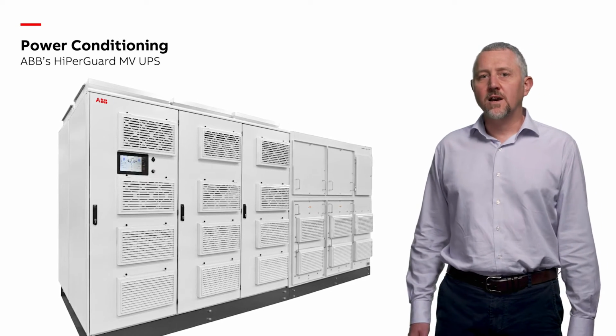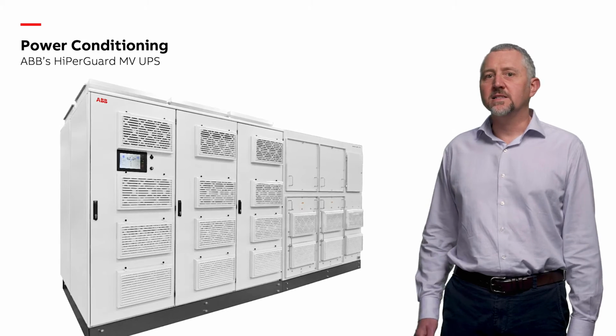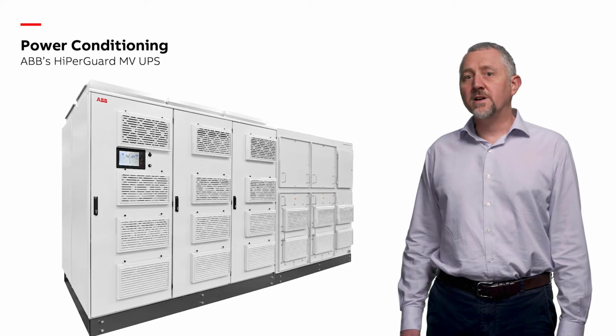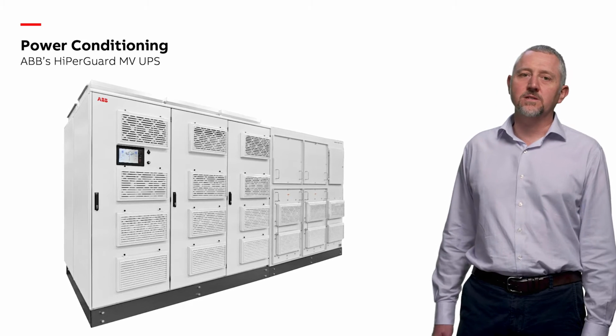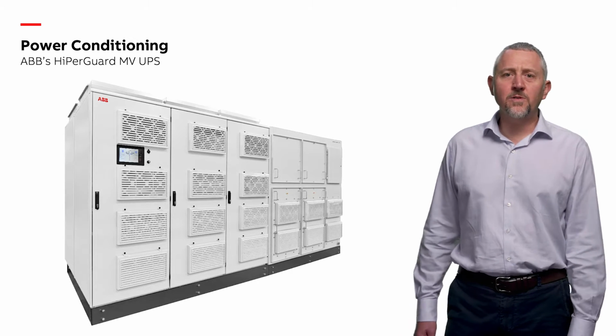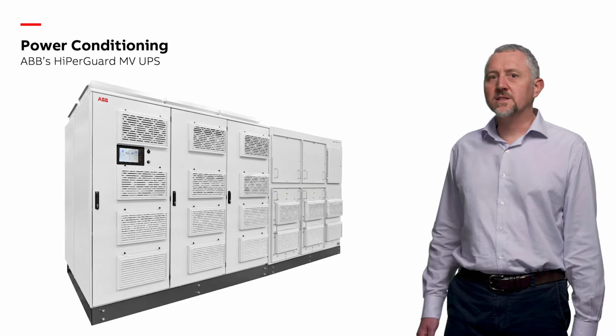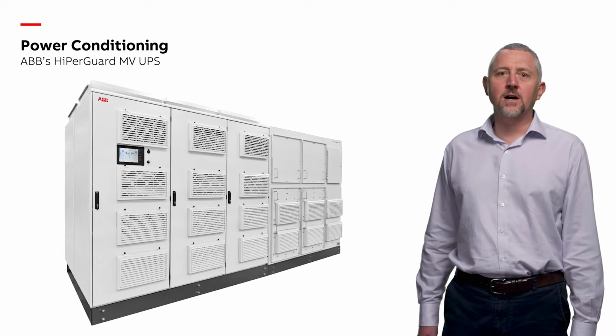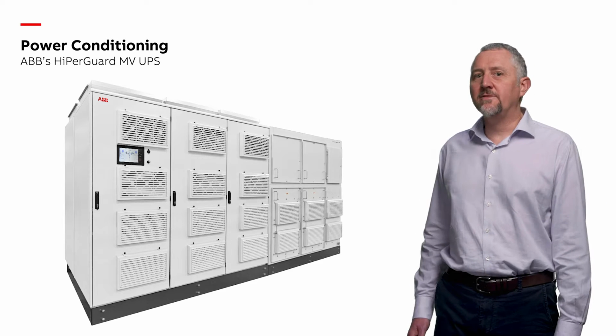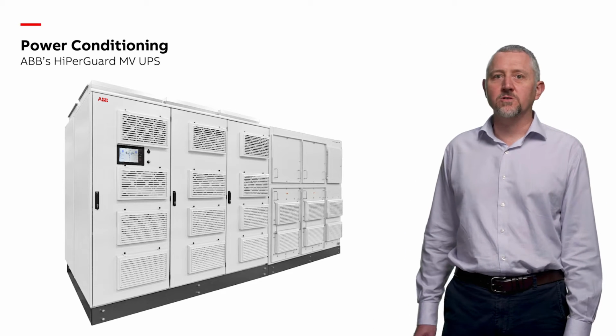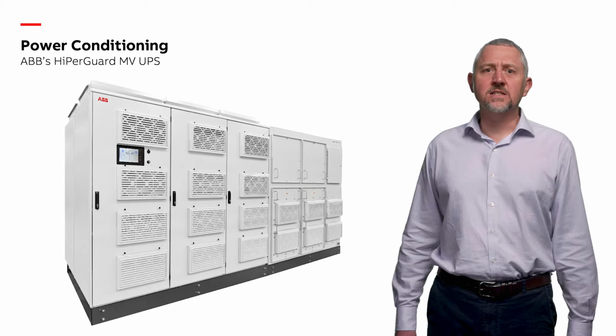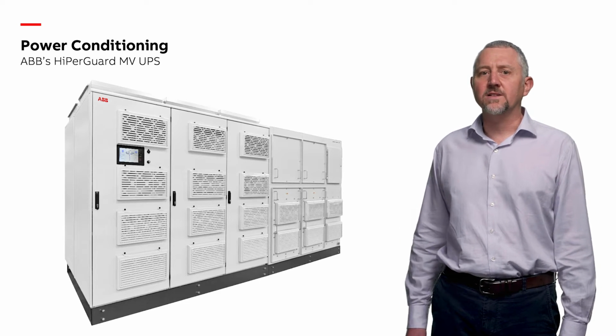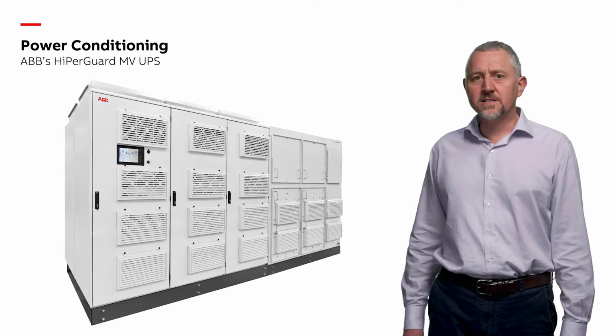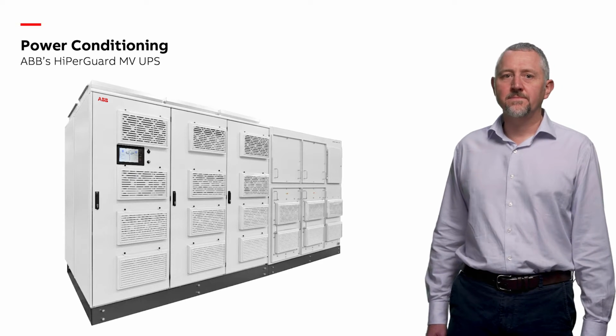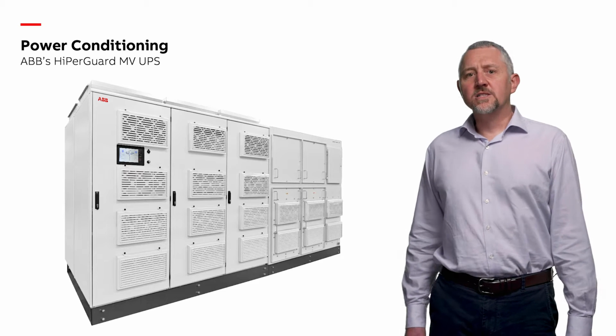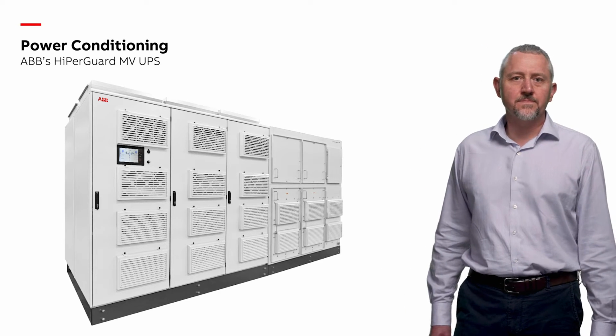Positioning at medium voltage, the isolating line reactor and coupling transformer simplify maintenance, while the power converters and energy storage operate at low voltage. The HiPerGuard's 2.5 MVA system output prioritizes redundancy through ABB's modular approach, allowing seamless operation even with 1, 2, or 3 inactive modules. Paired with modern energy storage, the HiPerGuard provides autonomies ranging from seconds to minutes, making it a versatile solution for critical facilities. For a closer look, let's check out our introductory video.